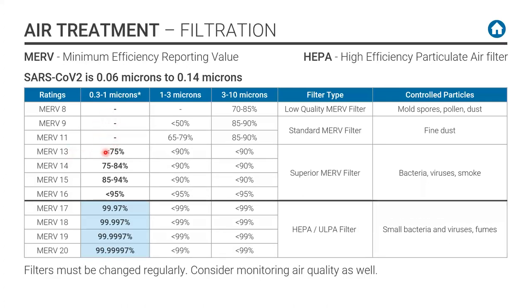Filters less than MERV 13 do not have a measurable quantity of small particles that they remove. So a fan coil unit, a VRF unit, smaller incremental units may not have good filters. An air handling unit, typically 4x4 units, large units can handle MERV 13 and work, because remember, the denser the filters, the higher the pressure drop.